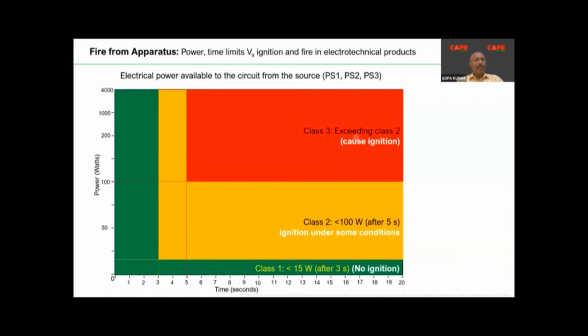So basically, when there is a fault, we have certain time, in seconds, to safeguard our property. For example, in the first case, we have 3 seconds. If the protective devices operate within this particular time, of course, you will have a spark, but nothing happens. The protective device trips and there is no fire. And this is how an electrical installation has to be designed. Now, with respect to equipment, electrical equipment is designed and tested in such a way that these devices are not supposed to create a fire due to an overload or an internal short circuit. So these are very much ensured.